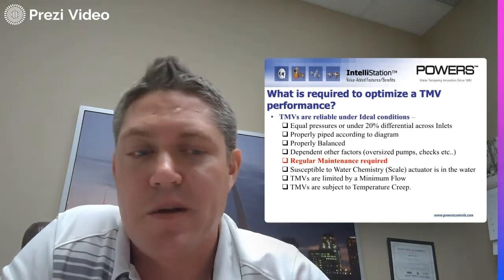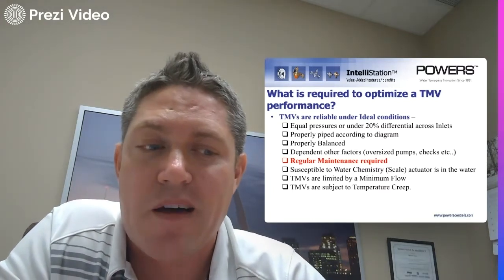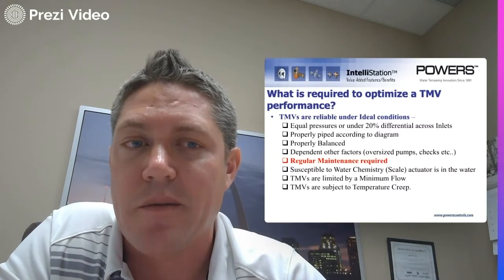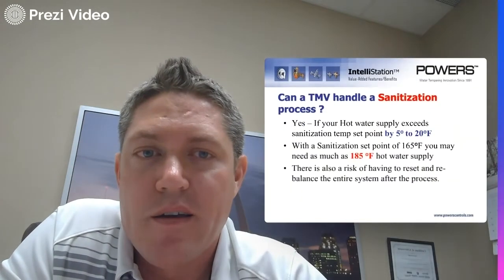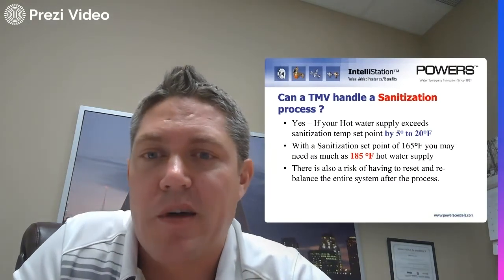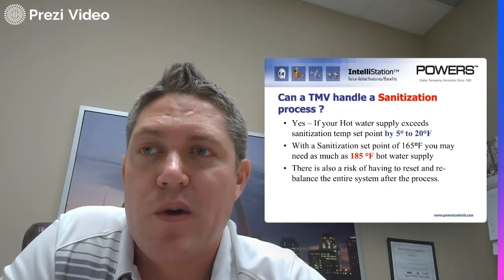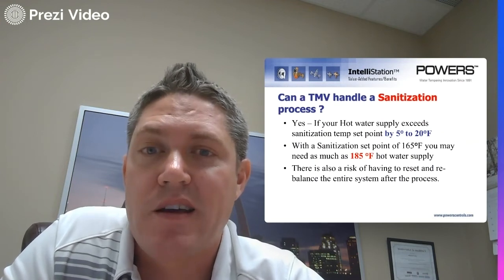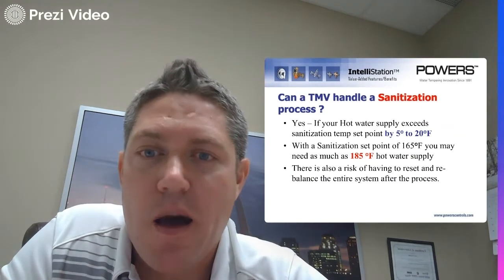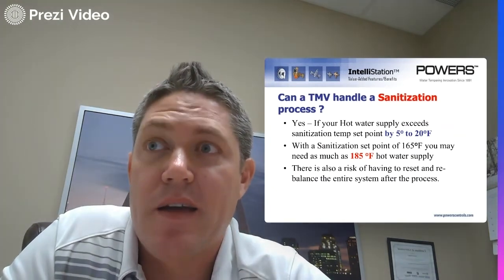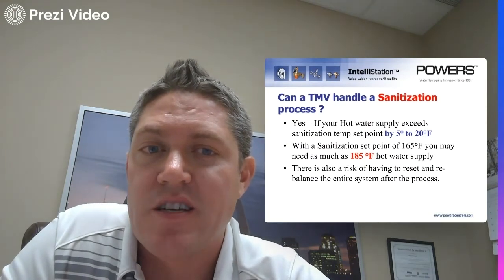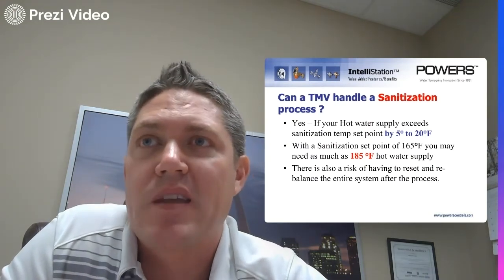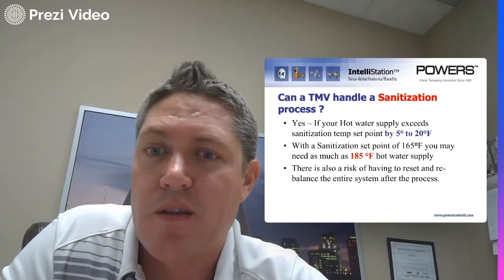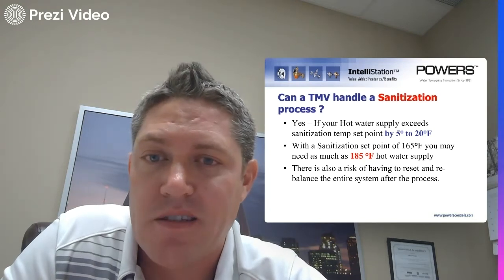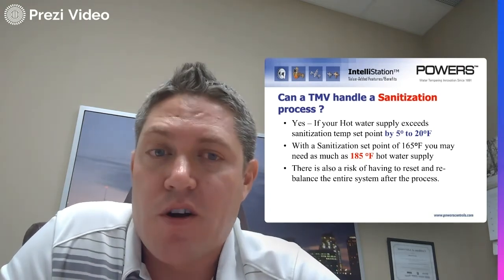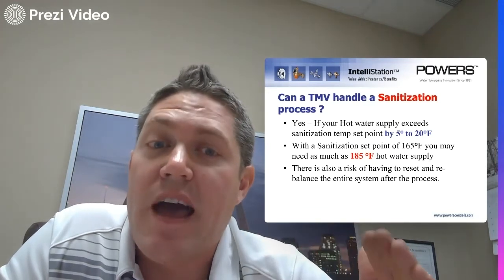And temperature creep, we talked a little bit about that. That's with that closed loop situation if it's not balanced properly. Those are all kind of drawbacks to having a thermostatic master mixing valve. Okay, sanitization mode. So this is becoming an increased hot button issue, especially with the awareness that has been brought to things like Legionella in a hot water distribution system, and other bacteria, other waterborne pathogens. Hospitals, VA centers, places with immunocompromised patients, those are more and more often looking at regular sanitization.